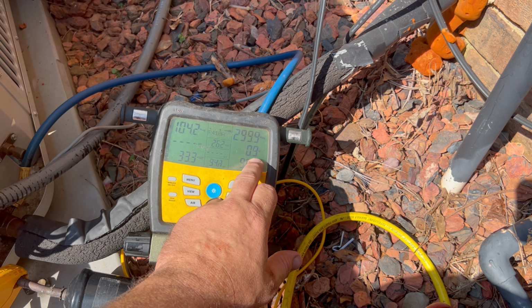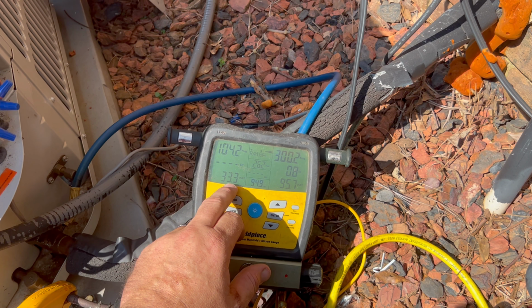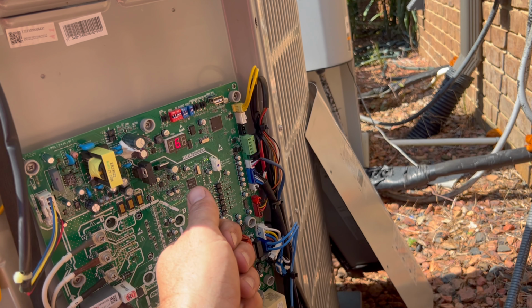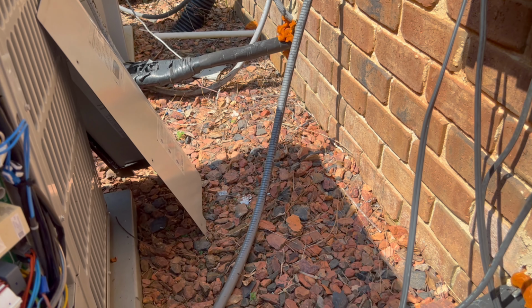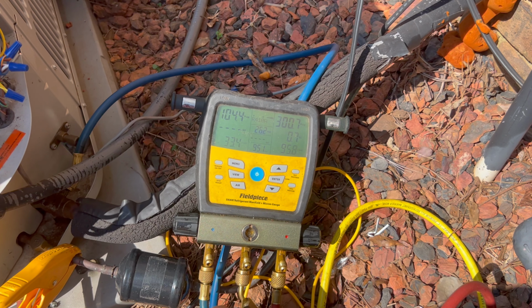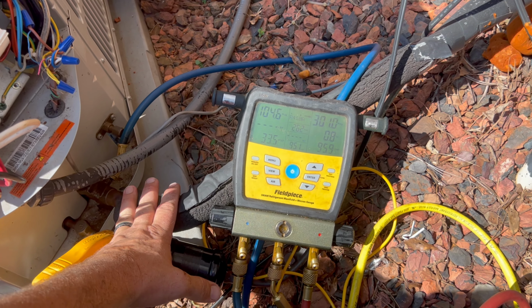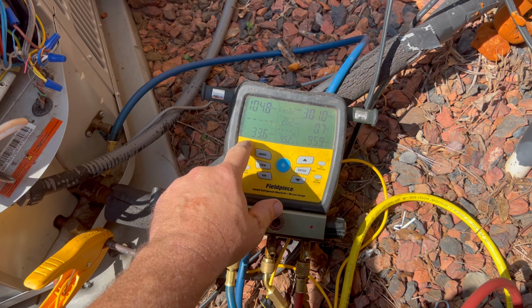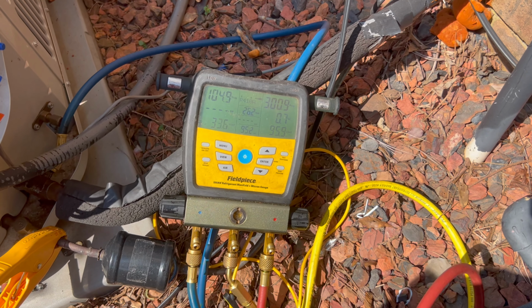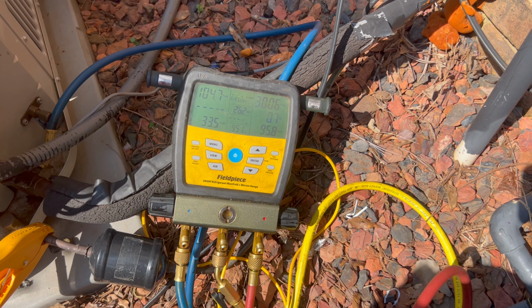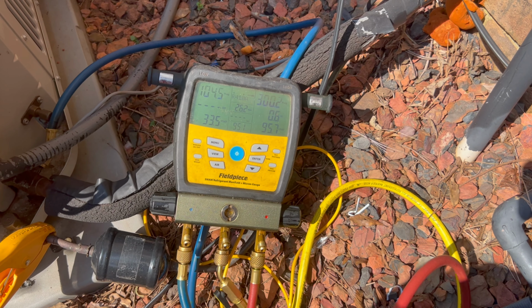So now that we're running a little higher into charging mode, you see we have very low to close to zero subcooling, and just at about freezing. We are slowly ramping up to 75% speed on this guy into charging mode. And you do have to remember, when we're doing this, we're bypassing all the normal features of this guy, where normally it would be monitoring the pressures and temperatures and adjusting this compressor to not allow itself to get down into this freezing range. So again, it's something to watch for when you run up upon these in the wild and look at it and say, well, refrigerant looks good, I'm done. It's just not cooling well, it's too hot, I guess. That's because you're probably only running 20 or 30%.